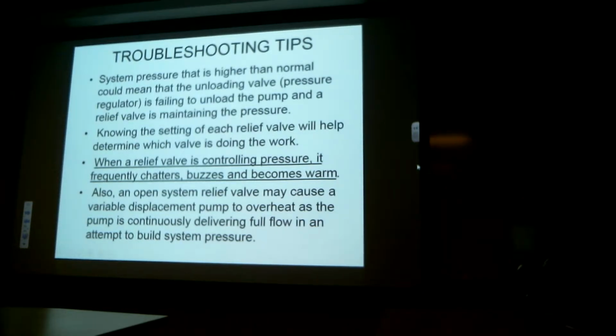If the relief valve is buzzing or chattering, in some designs what that means is that the relief valve is doing what it's supposed to do. It's buzzing and chattering, opening rapidly and closing rapidly to control system pressure. Additionally, a lot of relief valves will be warm as a result of doing that.